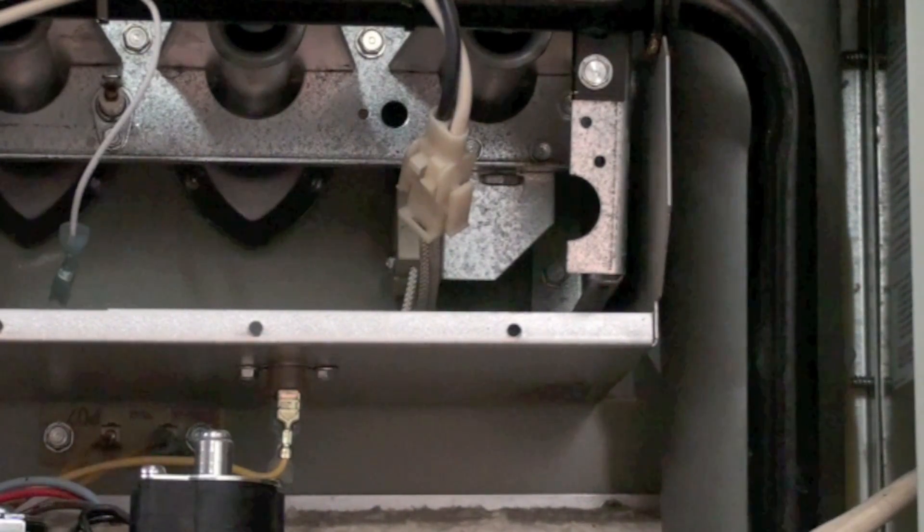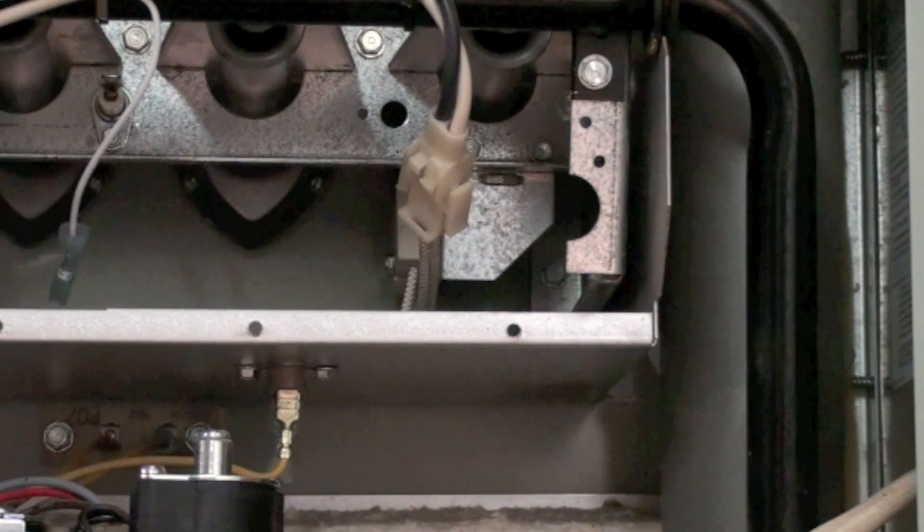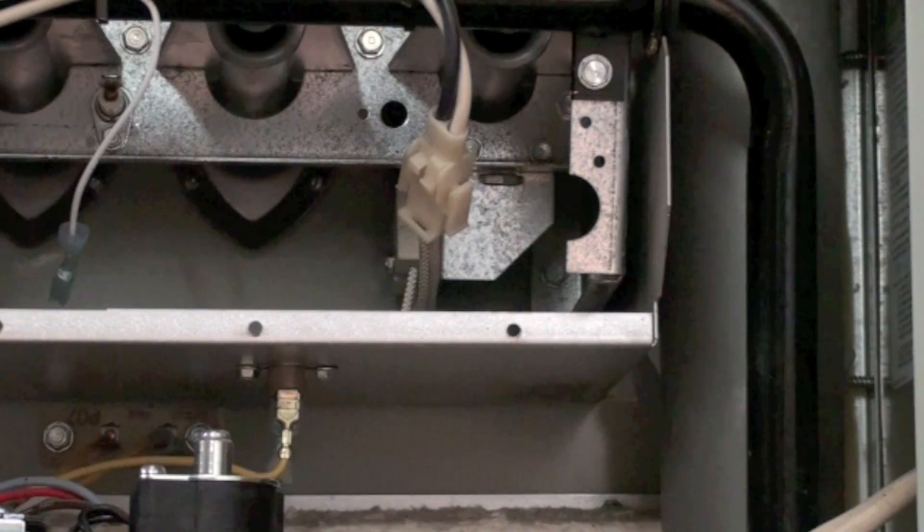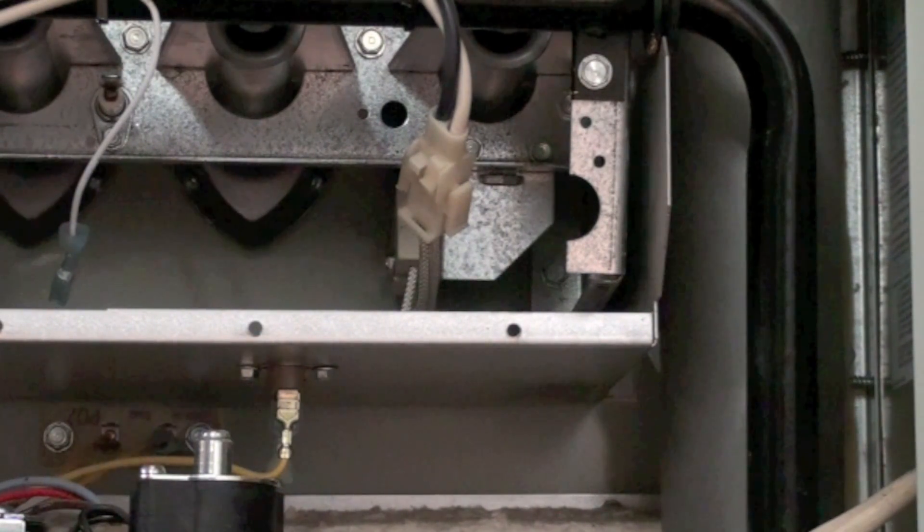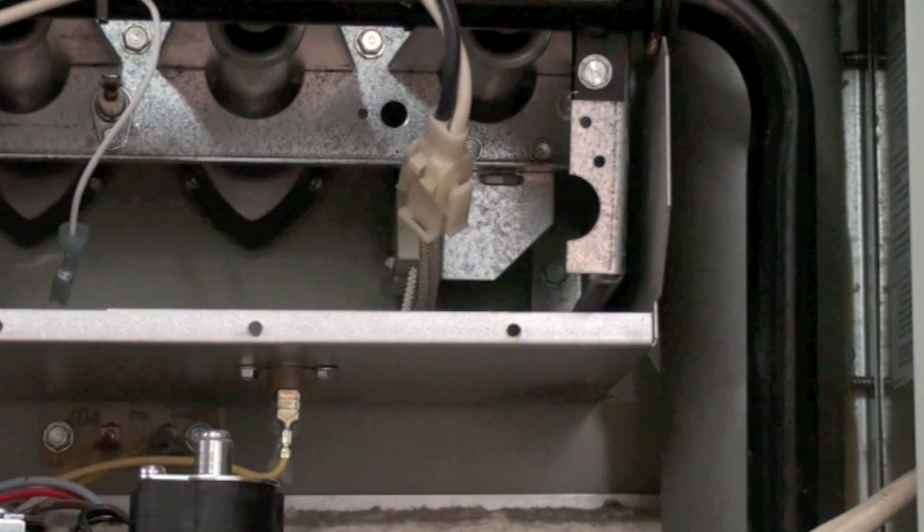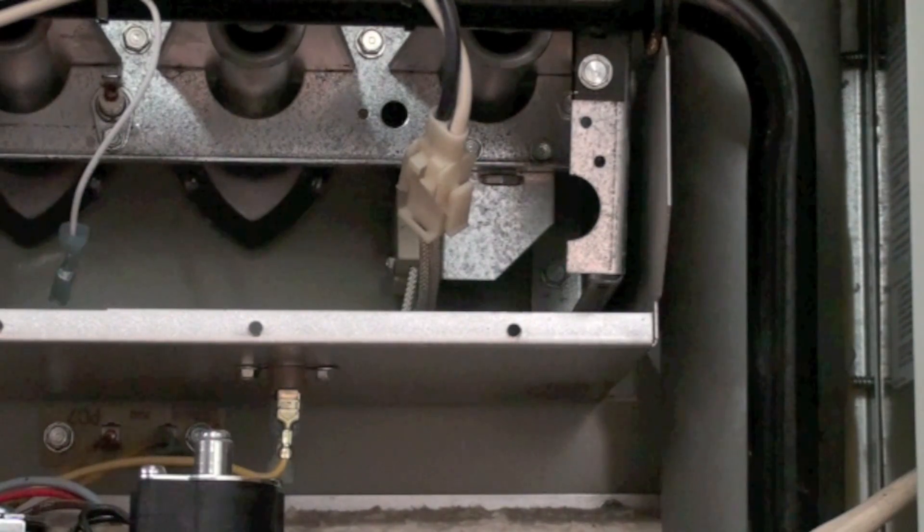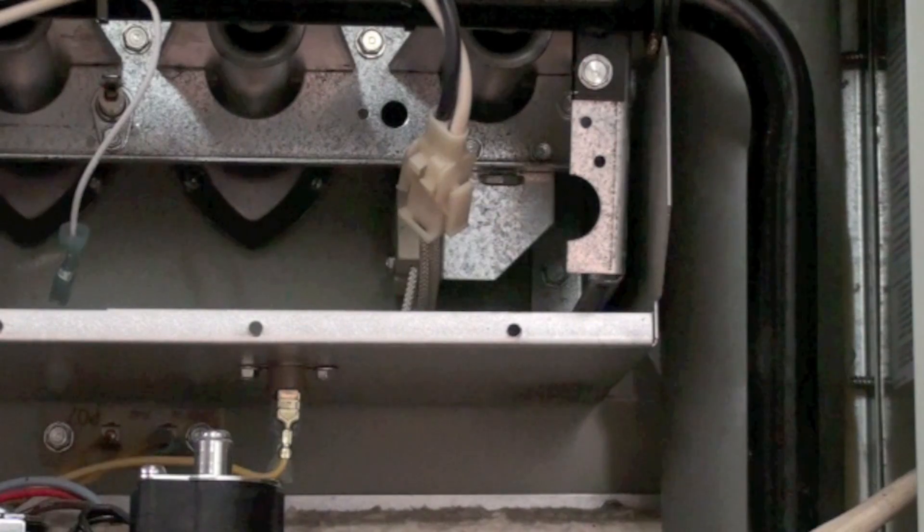I've seen a lot of them vary between 0.2 and 0.6 microamps. That's the number they read, and sometimes they'll fail, sometimes they won't. Most these things should prove at a half a microamp. Well, just clean it up, put it back in. That may solve your problem, very commonly, especially with an 80% furnace. That will solve the problem.